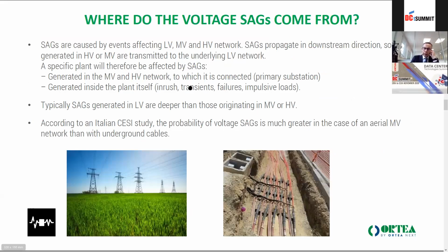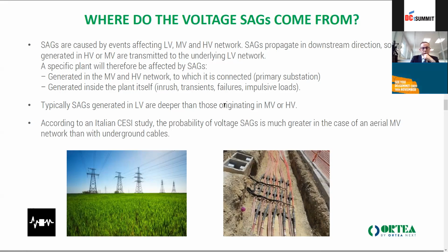So the sags are usually events that affect the medium and high voltage network, but they are also propagated directly downstream to the low voltage side. So mostly these sags and swells can cause troubles on the low voltage side more than on the high and medium voltage side.